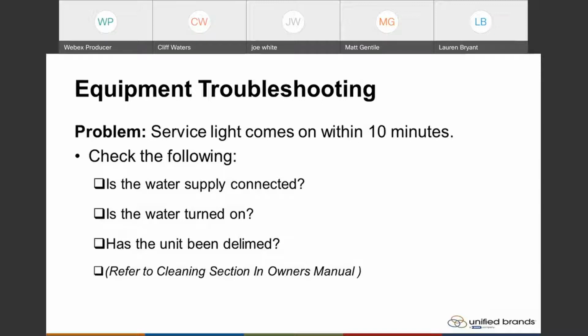So in order to get you back up and going, check to make certain the water is turned on. Then we're going to talk about whether the unit has been delimed. That is grossly important, especially on the HyperSteam unit, because it uses probes enclosed in a boiler that you can't see. If they become limed up, you can't necessarily see them like you can on the Smart Steam with the open reservoir and the shiny polished steam lid that I said should be removed. Yes, that one. So make certain the unit is delimed, and always refer to the cleaning section of the owner's manual when in doubt.